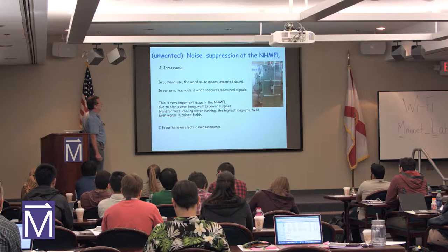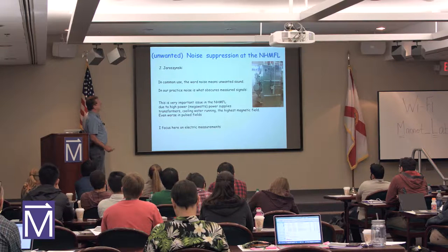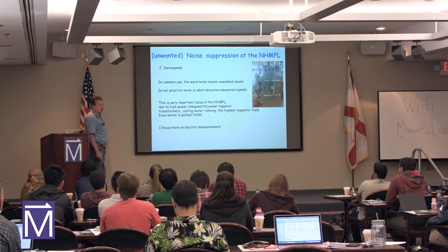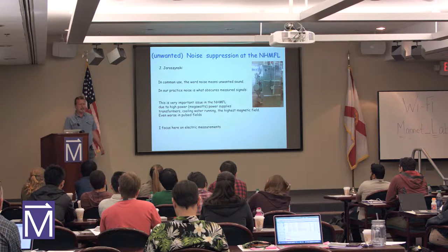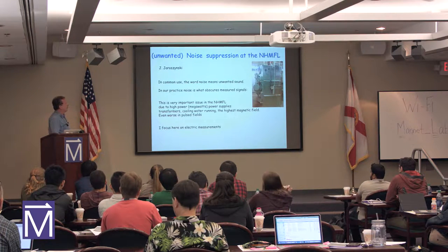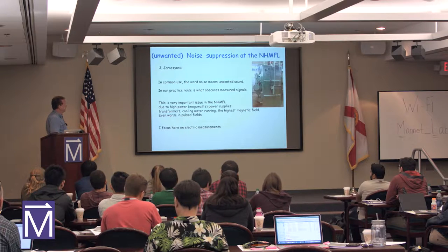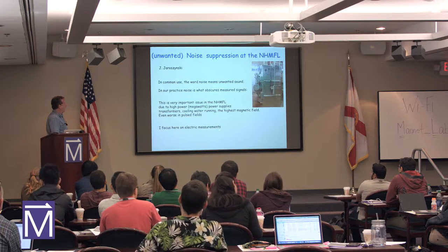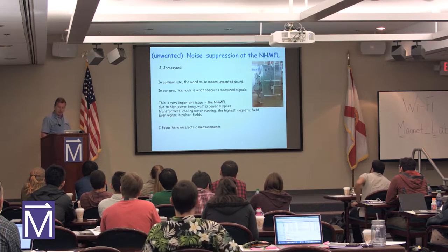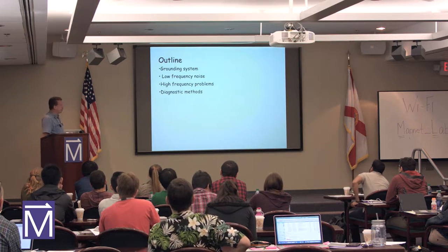This is one of our transformers. We have 8 of them, and generally the power installed in the DC magnet area is something like 50 megawatts or so. Magnets plus pumps, this is really high power. I will focus here on electrical measurement only.